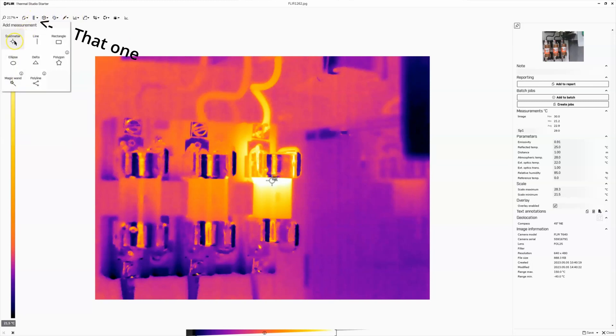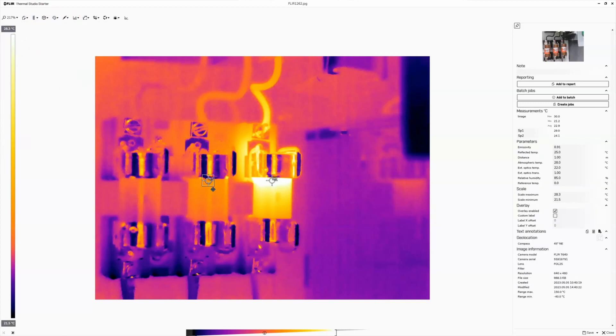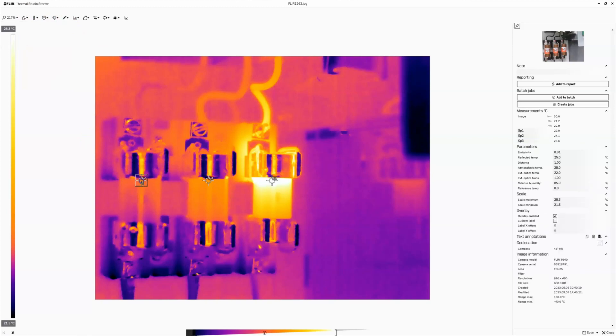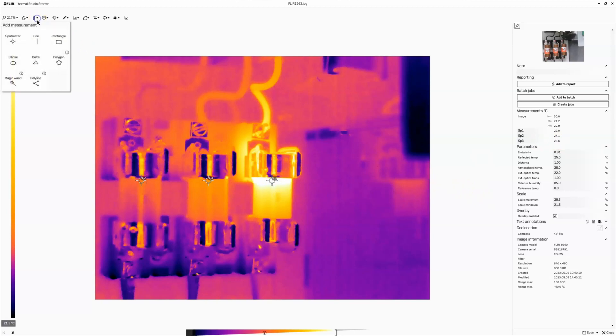And I really want to do comparison spots. Because I want to compare all three phases to each other. So this phase, or the C phase, spot one is 29 degrees, spot three is 23.6 degrees, right? So I can very quickly make a comparison like that. And I make it really easy to see on the report that we're doing a comparison by adding more spot meters.